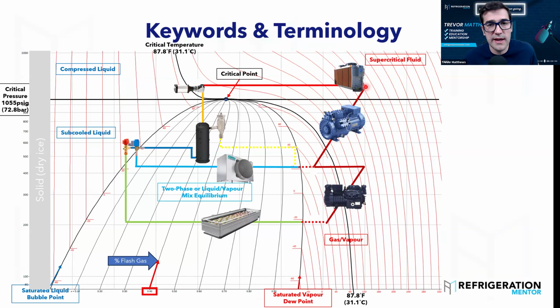It's going straight out to that gas cooler, because we know right now we're above the critical point. We are in transcritical. This is a supercritical fluid going up to that gas cooler. Now, this gas cooler at this point is just cooling the gas. It's just pulling out as much heat as possible to get us closer to the condensing point, because we can't get to condensing because we're above the two points, the critical pressure and critical temperature. We're above that critical point. So what we're doing is cooling it down as much as possible.